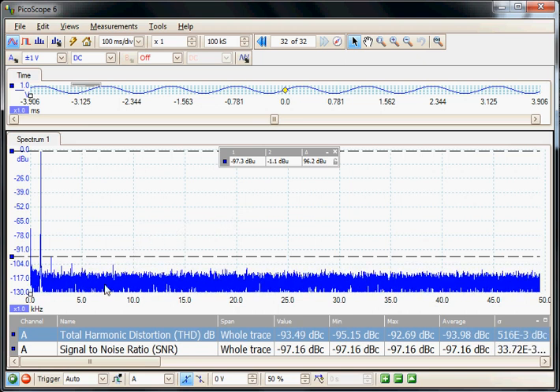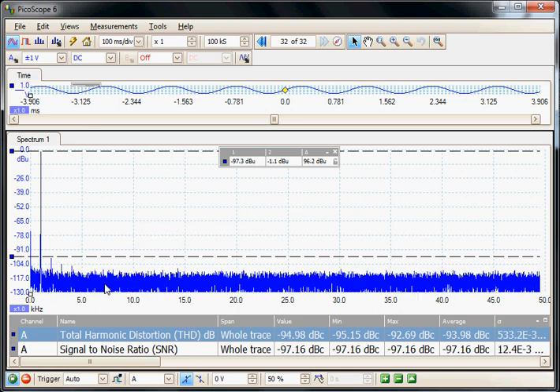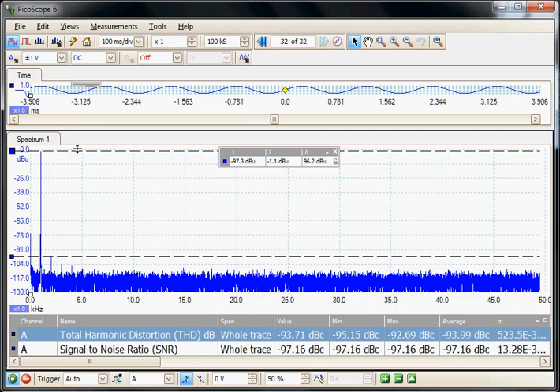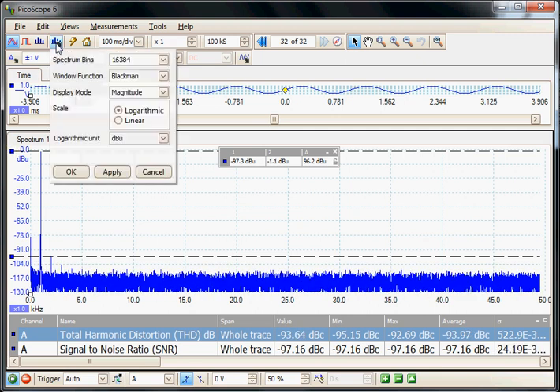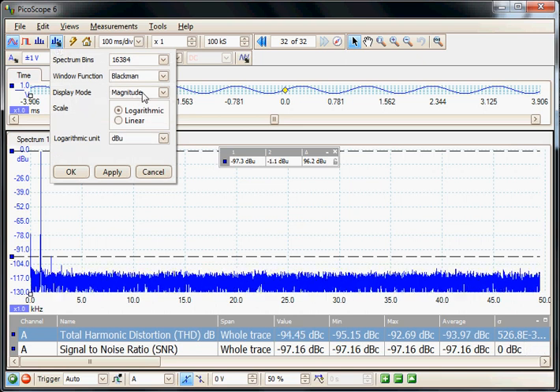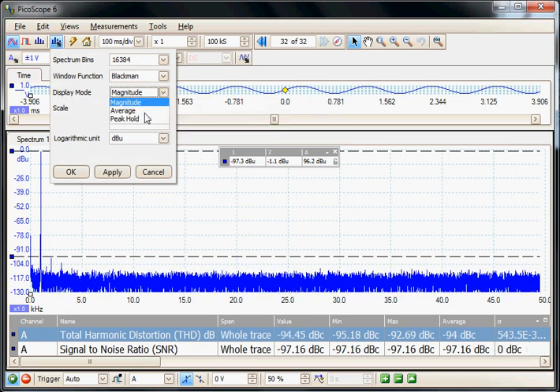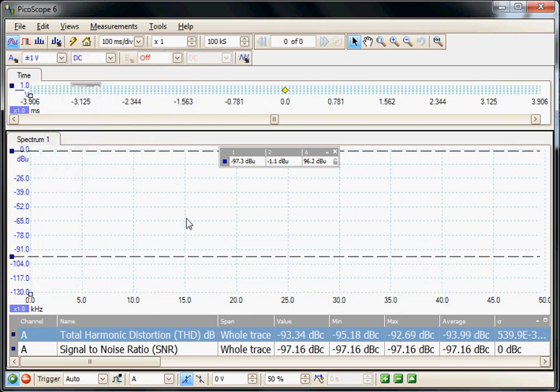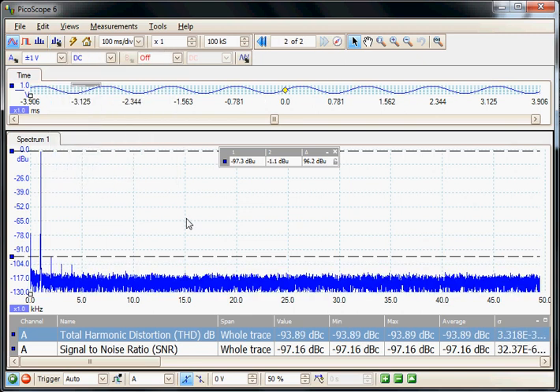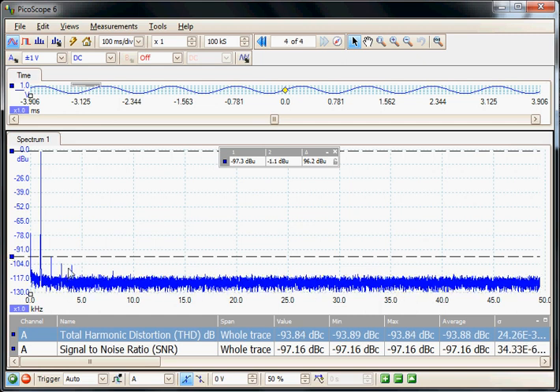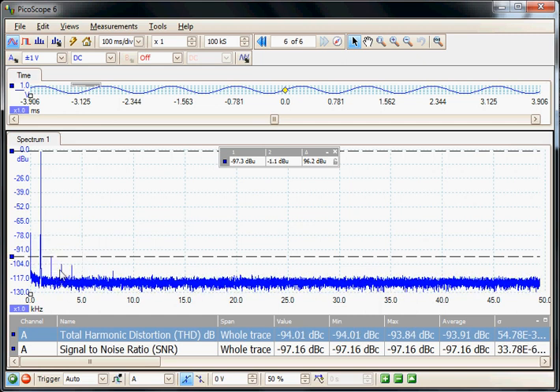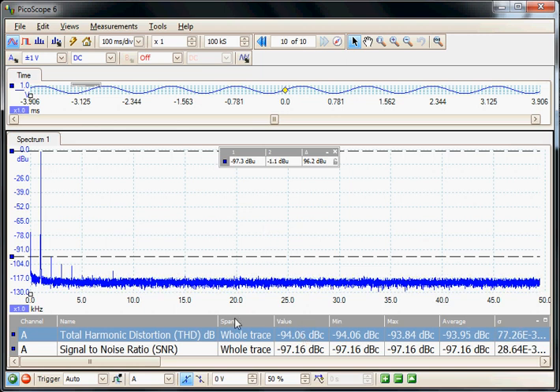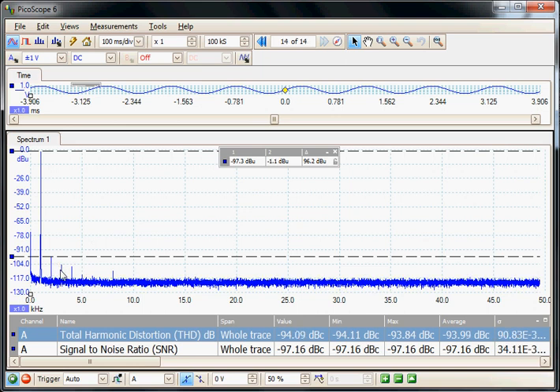The noise floor is below that but we can average out the mean noise. In the spectrum setup we can do an average of the acquisition and apply that measurement. So this will reduce the noise floor and give us more resolution on the harmonics. But we can see they've not actually changed, they are still down at minus 93 dBs. So the predominant factor in this particular measurement is the second and third harmonics.